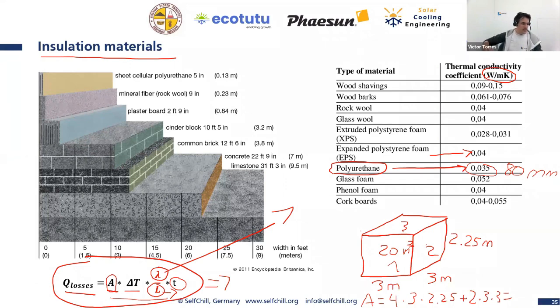Thank you very much, Charles. 63 square meter surface, very nice, 63 square meters, wonderful. Now we have this value, delta T. Let's suppose we have 30 degrees outside and 10 degrees inside, a worst case scenario. Actually we should take an average temperature; in Lagos, for example, that would be 25 degrees. So delta T becomes 25 minus 10, which is 15 degrees.